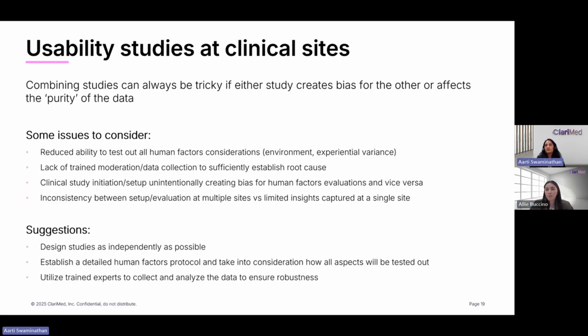Yeah. And I think in general, when we look at human factors validation, of course, when you're talking about a CLIA waived or an OTC, there isn't really any training. So when you're conducting the human factors validation, you have to account for that and not give your participants training. But the FDA wants the human factors validation to be as representative of the worst case scenario that will realistically happen. So for higher level medical devices where the company is providing training by default at a basic level, every user who ever uses this product for the first time will have had this training. That's something that also gets built into the human factors validation study where we have to simulate that training.